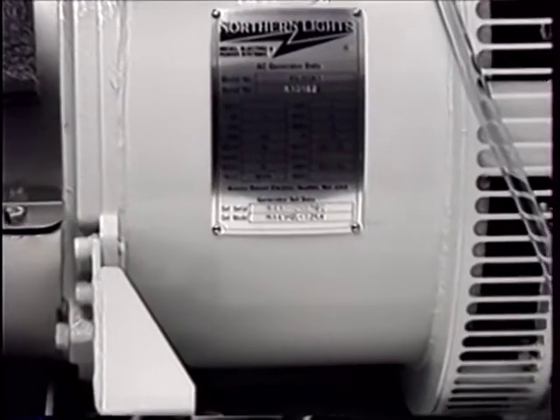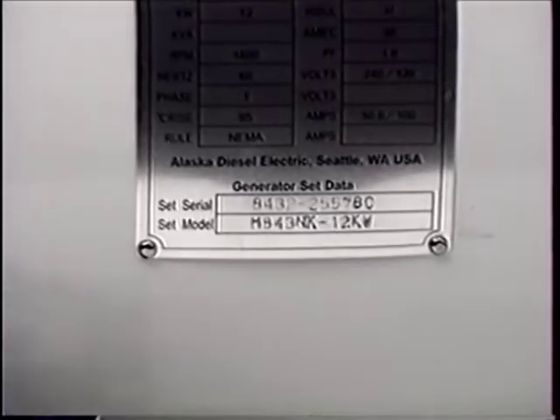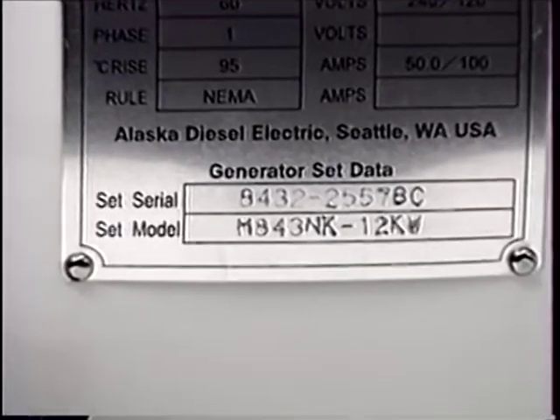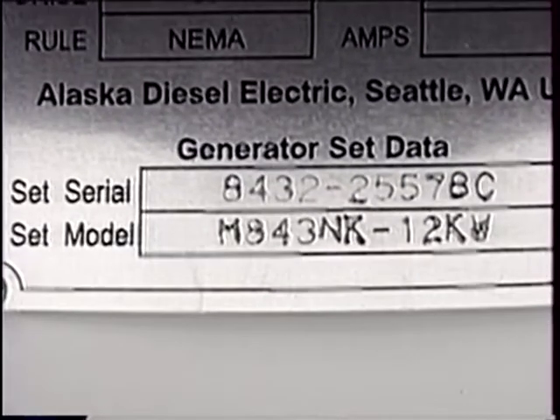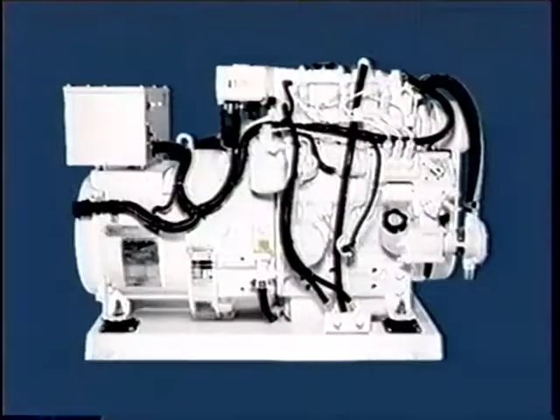Key to all product references are the model designation and serial number. These and other important information can be found on the data plate, which is affixed to the service side of the generator housing. Here we can see this generator has a model designation M843NK 12 kilowatt, and the serial number is 8432-2557BC.